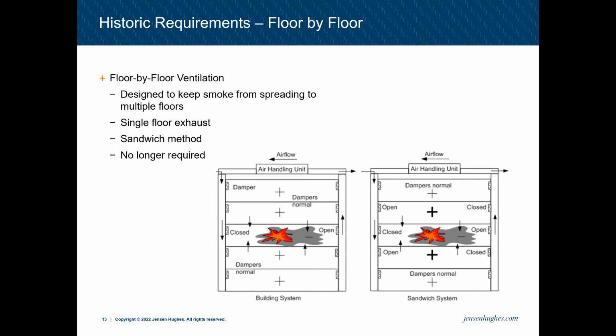The single floor is the floor of incident, or where the fire is located. We'll have an air handling unit switch to an exhaust mode and just exhaust that one space and close off all other supply and exhaust return dampers throughout that building. They would exhaust smoke from that area to keep it locally within that one floor. The other method was the sandwich method, which has the same sequence of operations as the other one. The fire or incident floor will exhaust, but the floors above and below will keep their supplies open from the air handling unit and basically pressurize the floor above and floor below, further keeping that smoke to that one floor. So there's no additional smoke movement throughout the building.